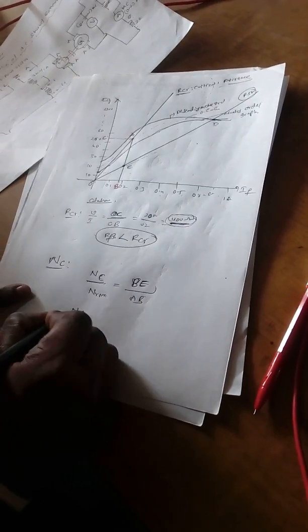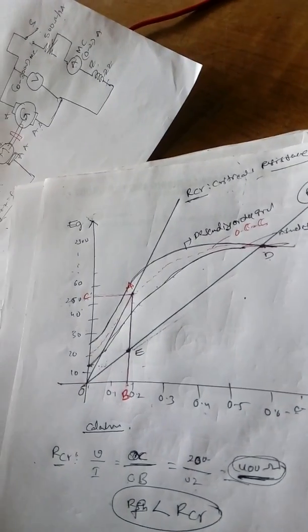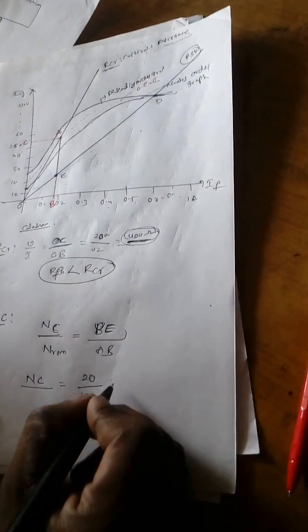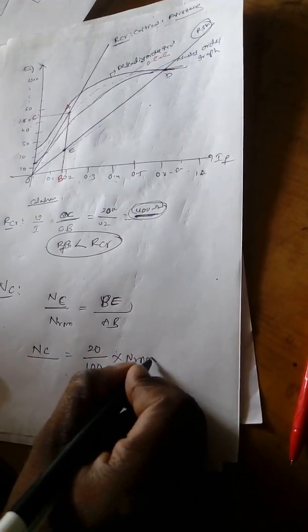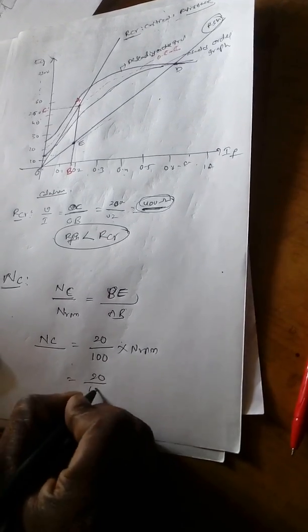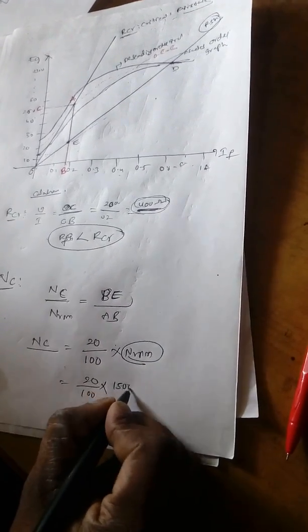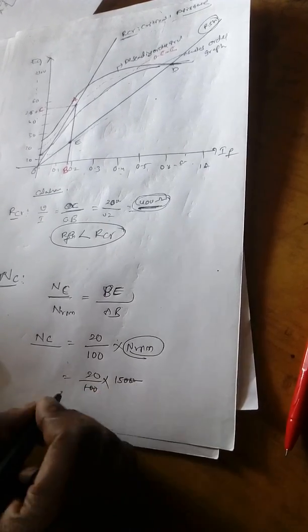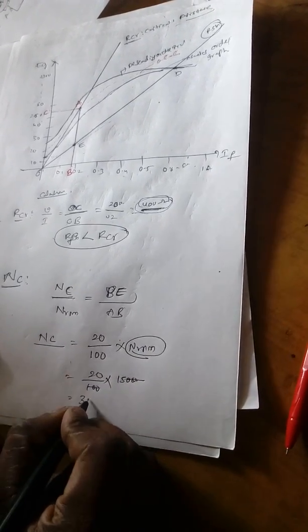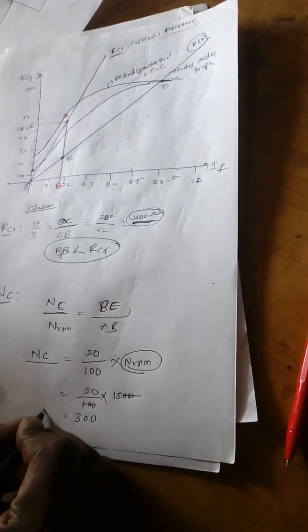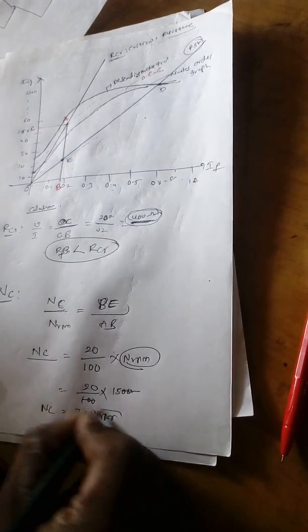Small voltage divided by total voltage. So NC, the critical speed, is BE — if it is 20 volts — divided by the total, say 100 volts, multiplied by N RPM. If the motor speed is 1500 RPM, then 20 divided by 100 into 1500: 100 cancels, giving 15 times 20, which is 300. The critical speed is 300 RPM.